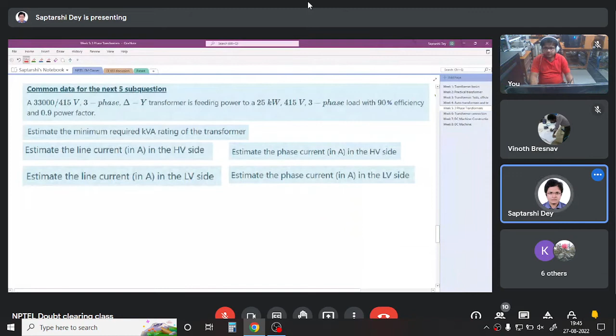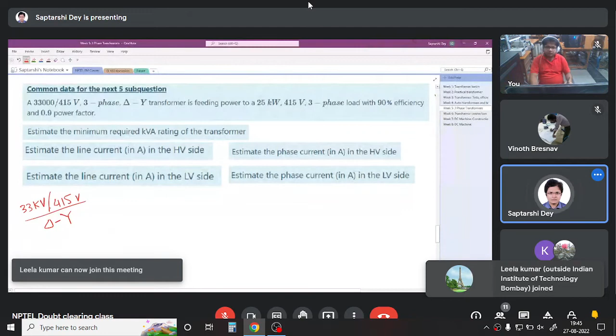A three-phase transformer which is rated as 33 kV by 415 volt, and it is a delta star connection. So what does it mean? When you say a three-phase line is rated at 33 kV, that means the line-to-line voltage is 33 kV. Invariably, if not otherwise mentioned, line-to-line RMS is 33 kV. And it is connected in delta.